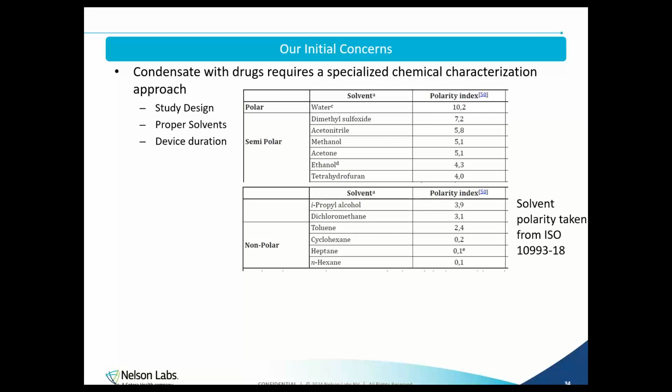While 18562-4 helps lay out condensate testing, what if the gas pathway can be used in anesthesia or some sort of drug or drug component? The standard only lays out water and then references 10993-18. This could be confusing for some in the industry, as now the list of standards to test and assess with the toxicological risk assessment are ever growing. Choosing the most appropriate solvent tends to be a challenge.